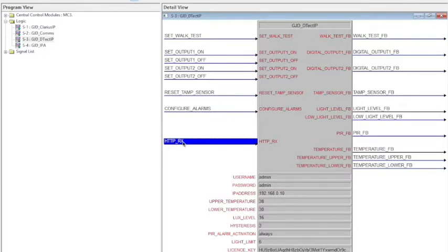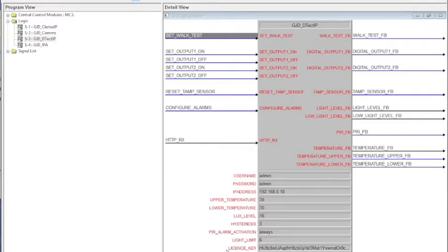If you recall, notifications from all devices are broadcast to all modules in the project, and this notification includes the IP address of the originating device. Consequently, each module knows which IP address it is controlling and can just filter out which notifications are for it and ignore all others. One really nice thing about the module is that it automatically configures the DTect device, so there is no configuration required on the DTect device itself. All the events are configured by the module.